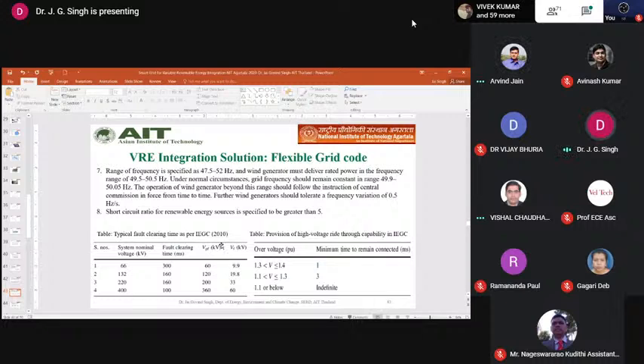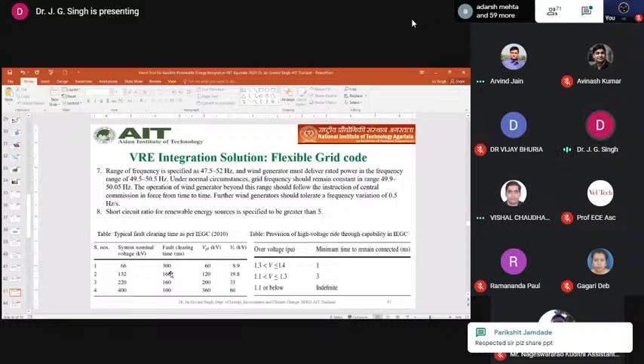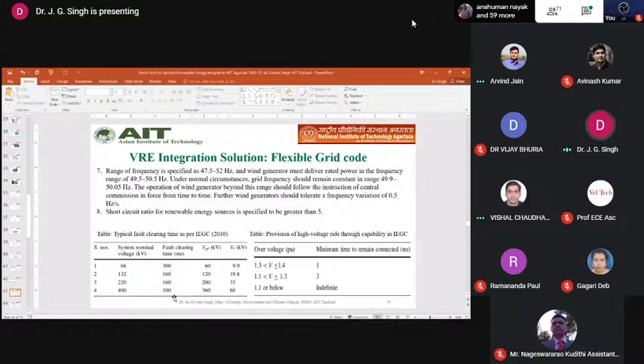Okay. And this is the lowest voltage. So these are the clearing times. For low voltage, 66 kV, they allow about 300 milliseconds. At 400 kilovolt, they only allow 100 milliseconds, and one cycle is 20 milliseconds, which means they allow 5 cycles at a 400 kV grid. And these are the time periods for which they are supposed to stay connected if the voltage at the PCC exceeds this range.